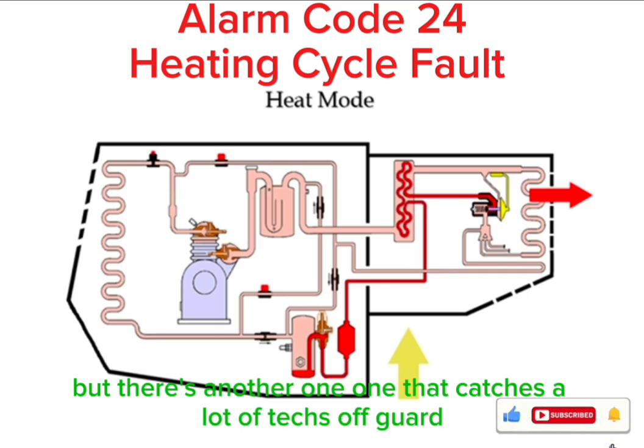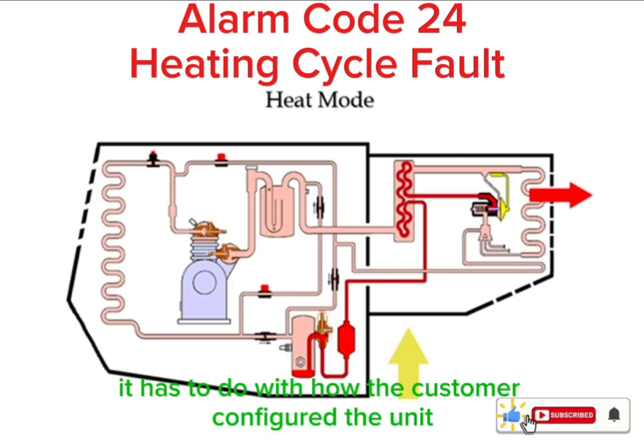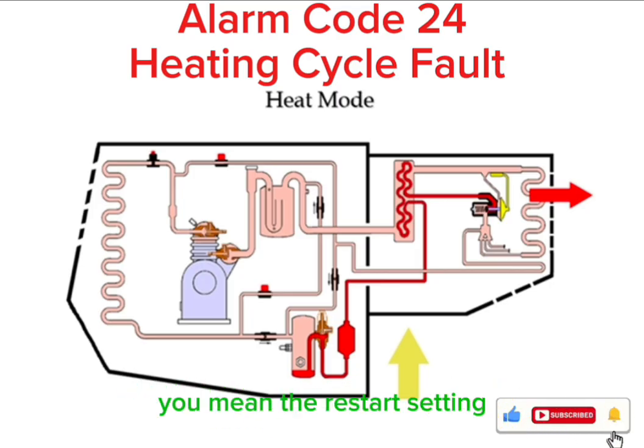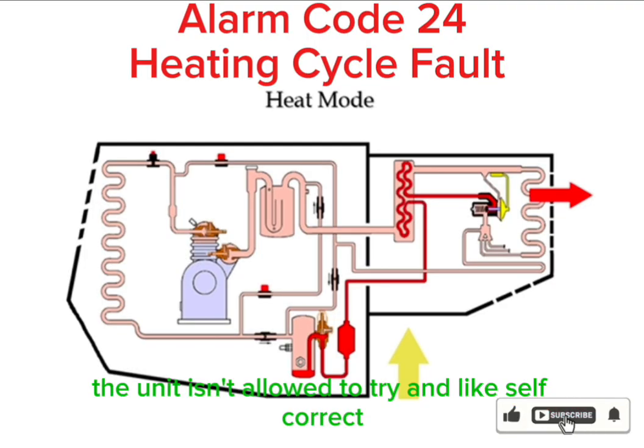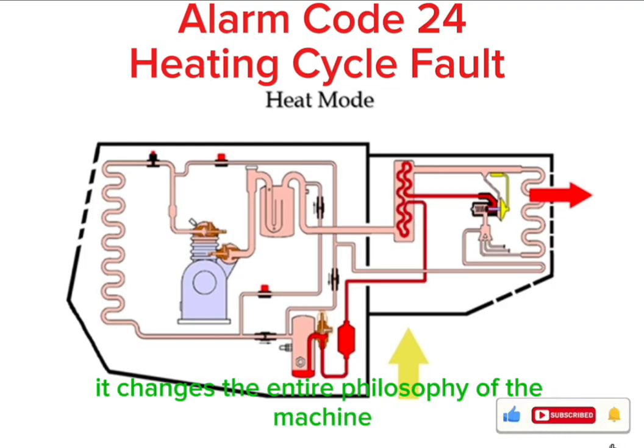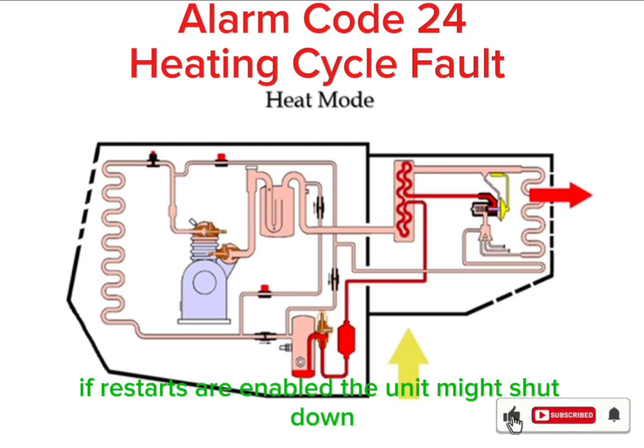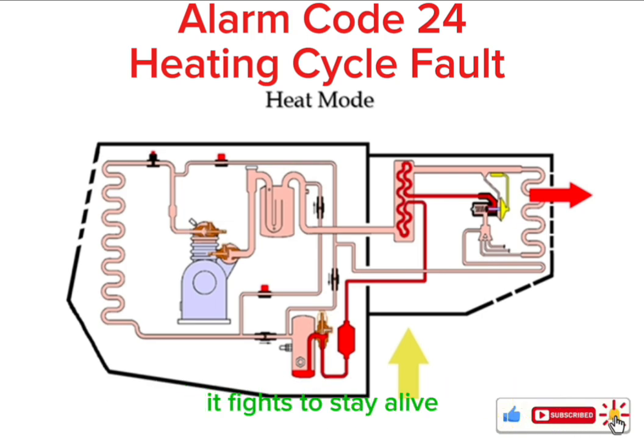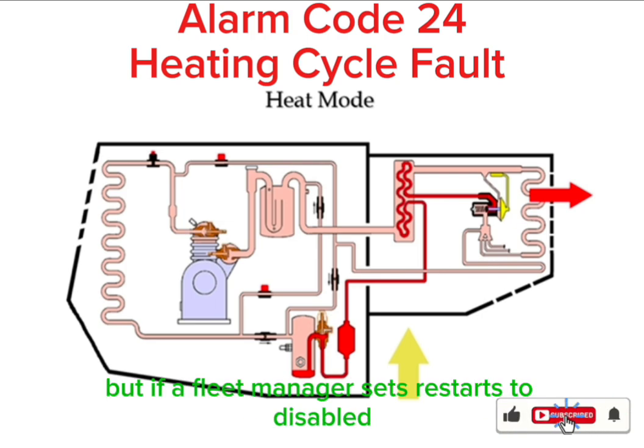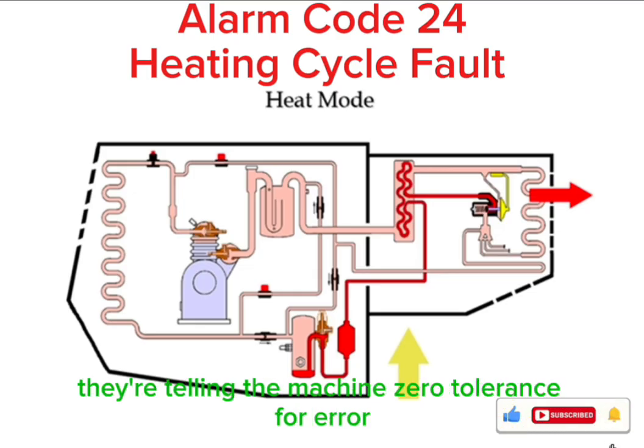But there's another one that catches a lot of techs off guard. It has to do with how the customer configured the unit. You mean the restart setting? Bingo. Restart's disabled. I've seen that in the menu. If restarts are set to disabled, the unit isn't allowed to try and self-correct. It changes the entire philosophy of the machine. If restarts are enabled, the unit might shut down, wait a minute, and try to fire up again. It fights to stay alive. But if a fleet manager sets restarts to disabled... They're telling the machine zero tolerance for error.